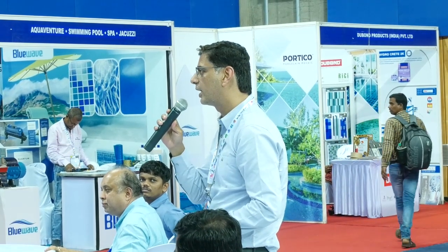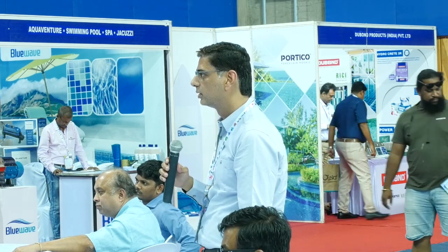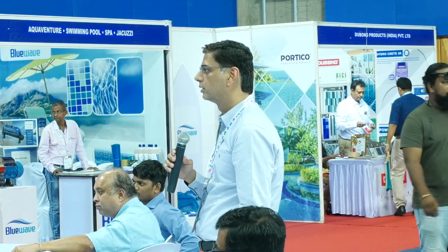Sir, how about the filtration turnover time? What is the ideal turnover time we should have in a swimming pool? For a spa, maximum 1 hour. For private pools, it can be 4 to 6 hours. For public pools, it has to be much faster.